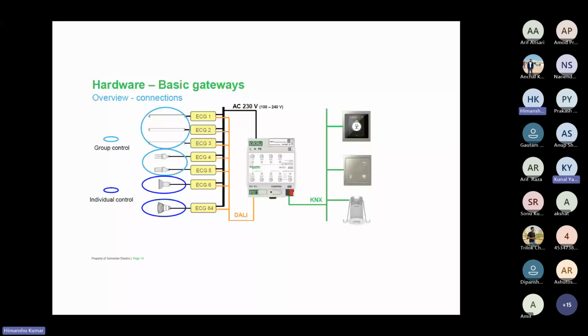So your wiring cost is reduced drastically. Just imagine if you have 60 lights on a floor - you would need 60 or more wires to control them individually. But with DALI, only one wiring loop goes from driver 1 to driver 64, and in the programming phase we can group them as per the need.